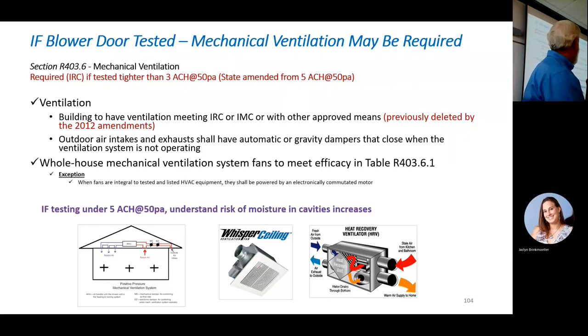And those fans have to meet a certain efficacy. I mentioned this fan as being a high efficiency fan. You cannot use that $13 cheap fan for this. Number one, it would drive everybody crazy and no one would ever leave it running. And number two, they would fail in about 3 months of continuous operation if they made it that long. So there's a table, and I don't think I put the table in here, that requires a certain efficiency on the fan.